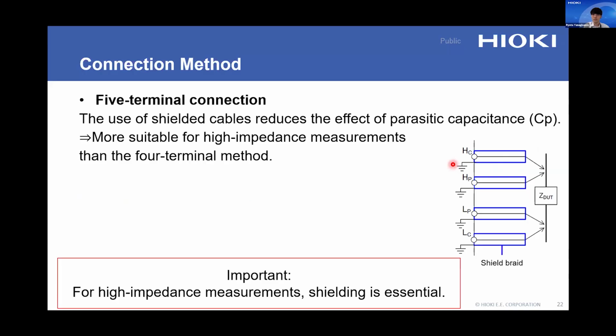For this reason, the 5-terminal connection uses coaxial cables to reduce the effects of parasitic capacitance. In high impedance measurement, shielding is fundamentally important. In addition to cables, measures such as using a shielded box are also very, very important.